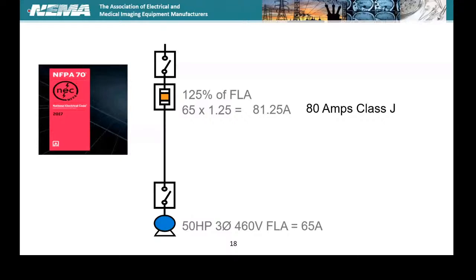Well, we have short circuit protection. And what I did here is I kind of ad-libbed on this slide a little bit. I put an example of, let's say that 80 amp fuse didn't quite make it. We are allowed to go up to 140% for overload protection on that motor. I did the calculation, and it comes up with 91 amps. And now I go back to a 90 amp Class J fuse, and I provide both overload and short circuit protection for this motor circuit. Yep.